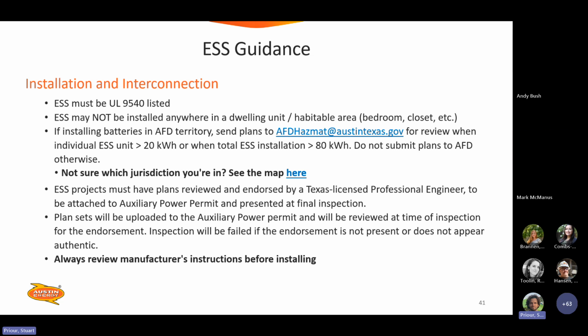A little more guidance on energy storage. All energy storage has to be UL 9540 listed. It can't be installed anywhere within the dwelling unit itself. If you're installing in AFD territory, you need to send plans to AFD Hazmat at austintexas.gov for review of individual ESS units. Each individual unit should not be larger than 20 kilowatt hours. When the aggregate system is larger than 80 kilowatt hours, that's considered a commercial project and it will need to go through AFD plan review. If you're not sure which jurisdiction you're in, that's a map that you can link to right there.